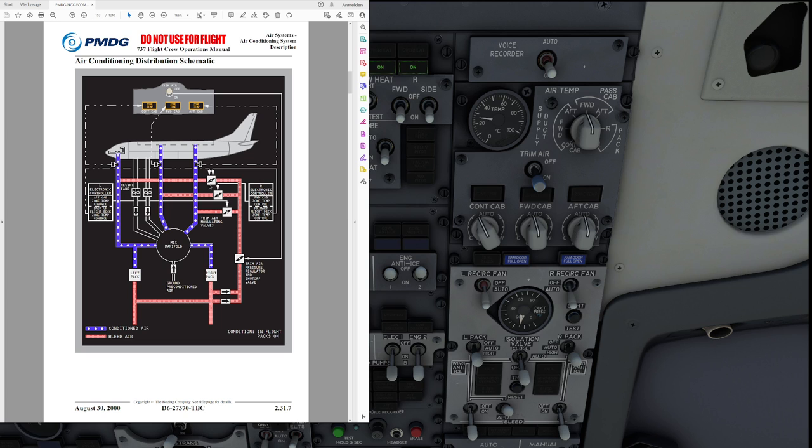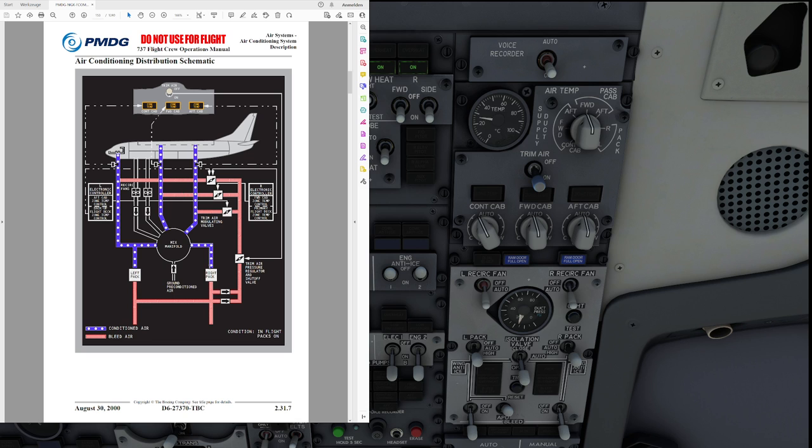Why are we doing this? Well, the 737-800 and 900 have a larger cabin so in order to reduce workload on the packs we are adding the trim air to the system in order to save a little bit more fuel over here since it will require less load on the packs since less cooling of the air has to take place.